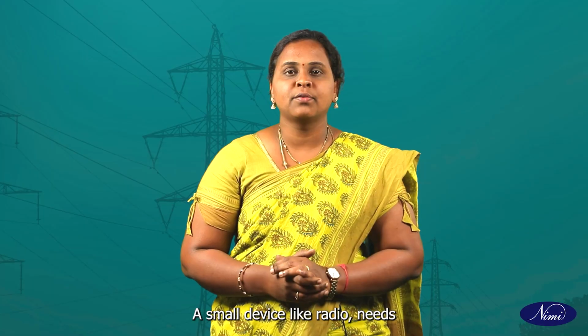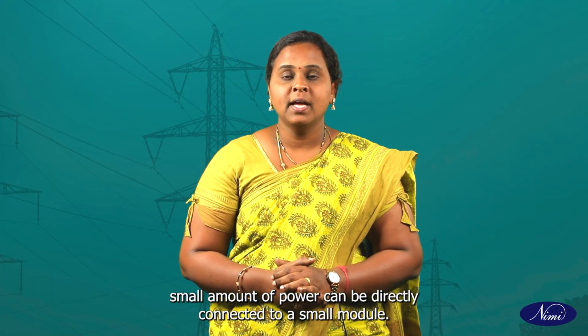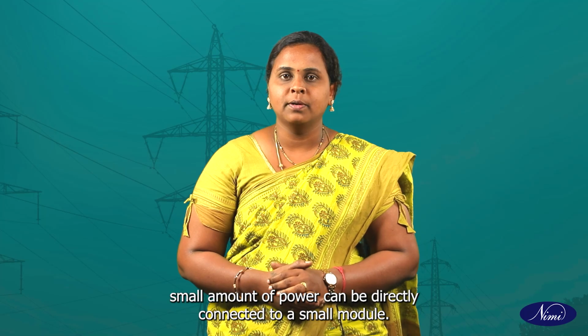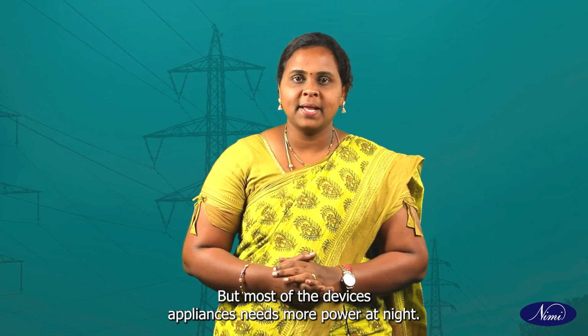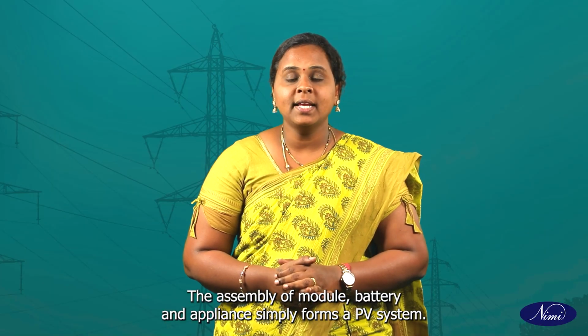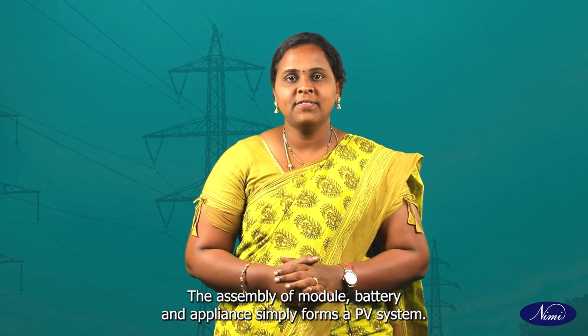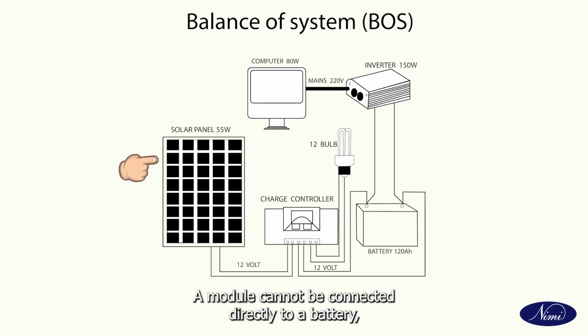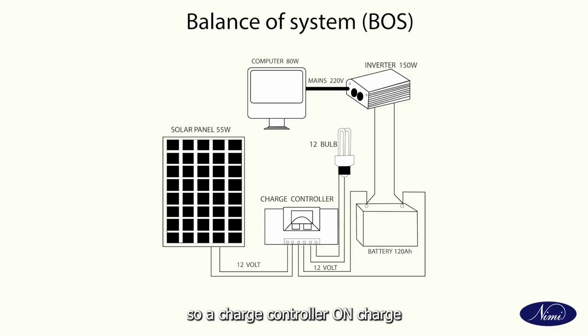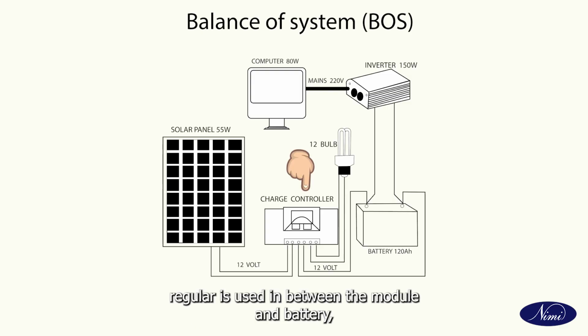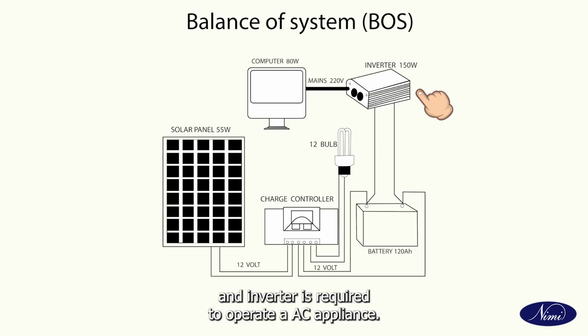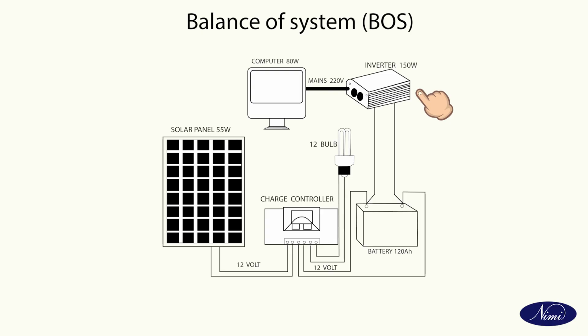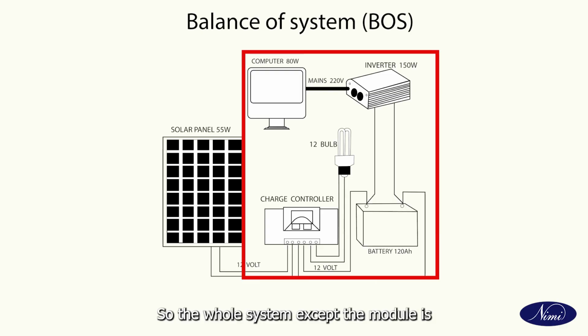A small device like a radio that needs a small amount of power can be directly connected to a small module. But most of the devices and appliances need more power at night. The assembly of module, battery and appliance simply forms a PV system. A module cannot be connected directly to a battery, so a charge controller or charge regulator is used in between the module and battery, and an inverter is required to operate an AC appliance. So, the whole system except the module is known as balance of system BOS.